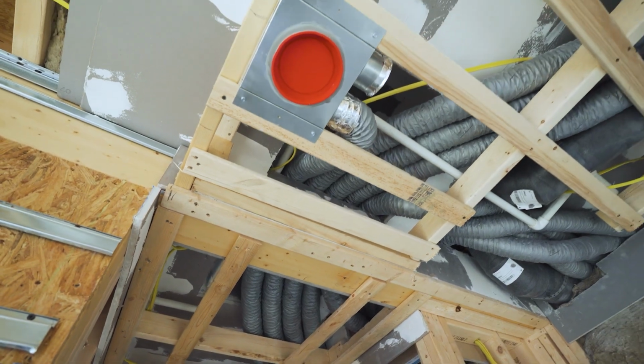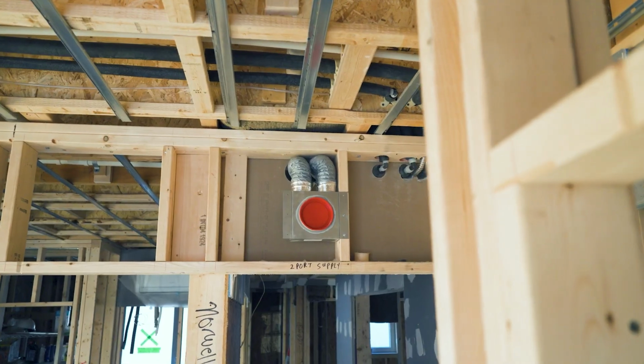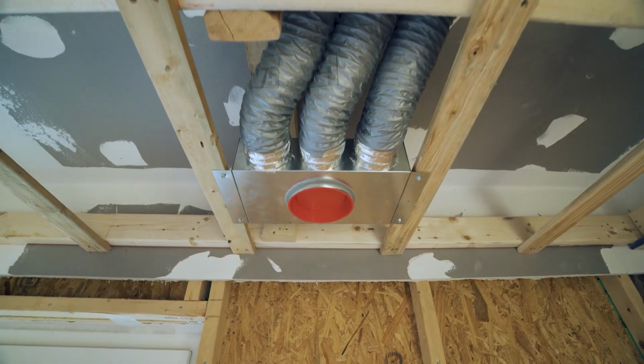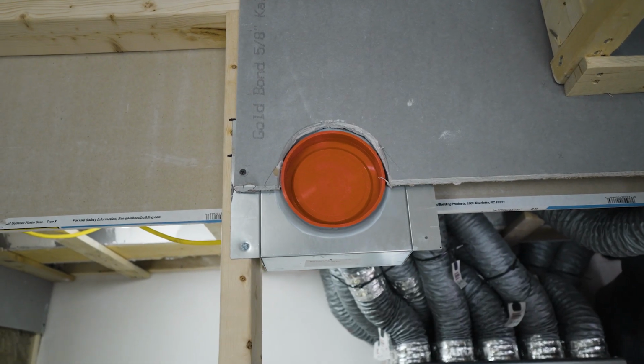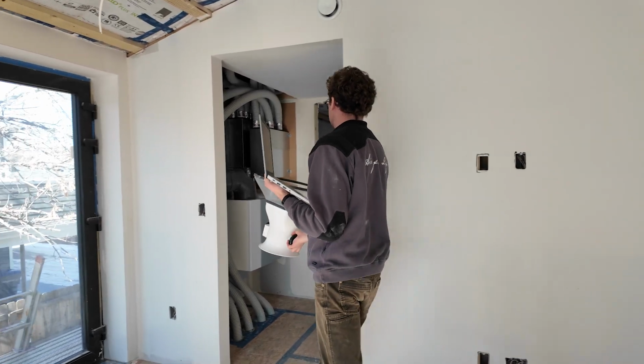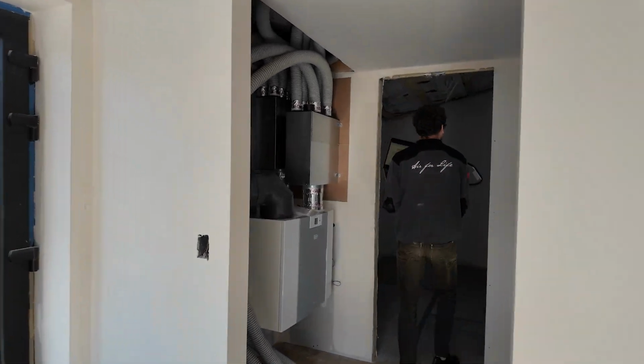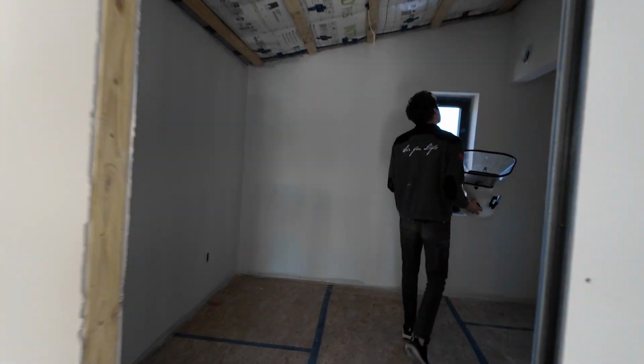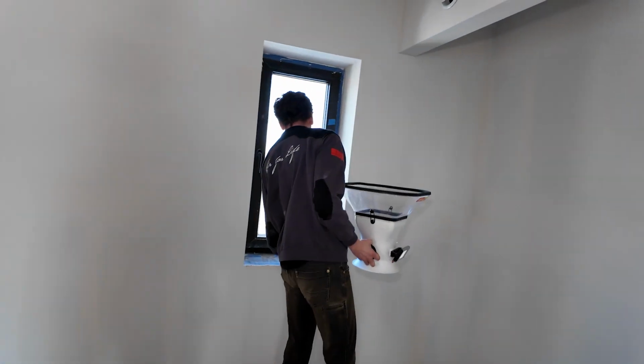Installers should keep the unit off and the distribution sealed while construction is in process to prevent dust and debris from entering the system. When the installation of the Brink FLAIR system and drywall are fully complete, the commissioning agent can begin their work. Before a commissioning agent comes on site, the installer or homeowner should complete the commissioning readiness checklist that 475 provides. This will help prevent any unforeseen circumstances or any big mistakes.